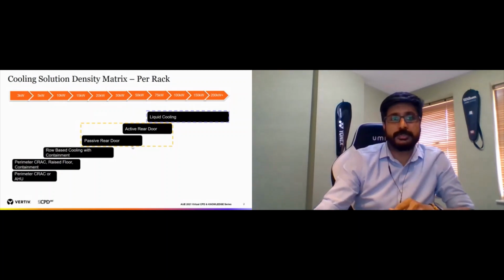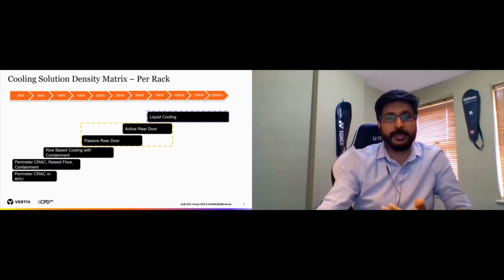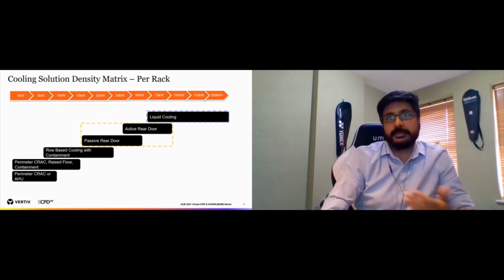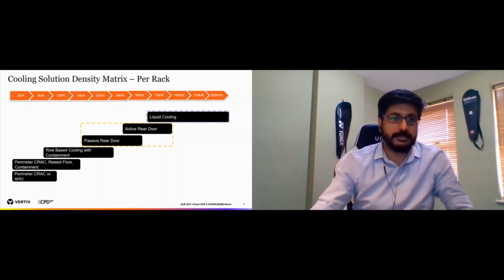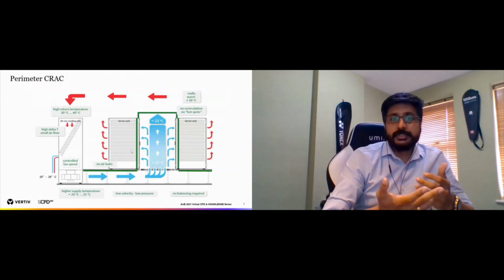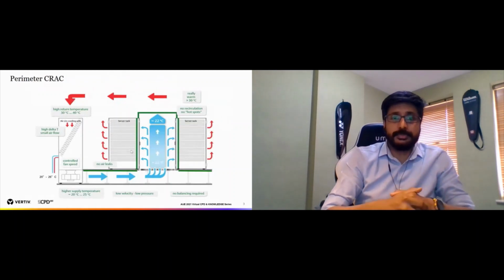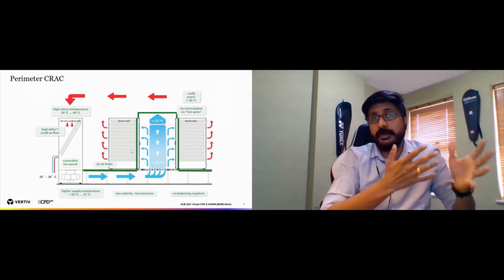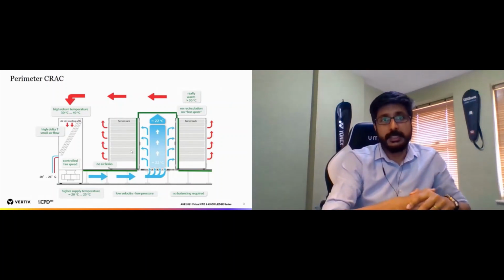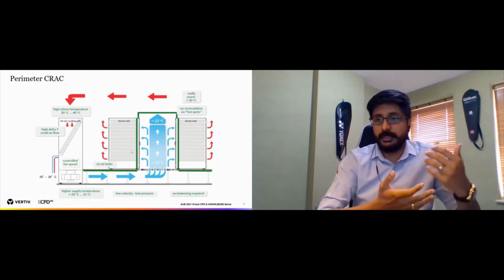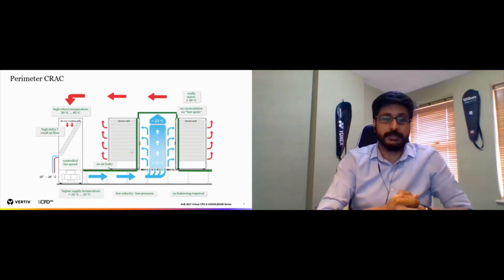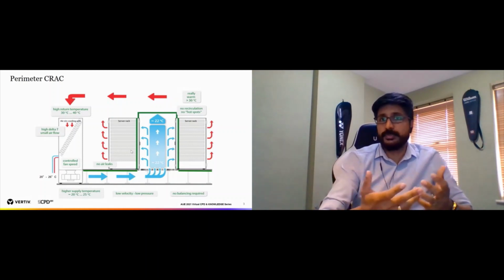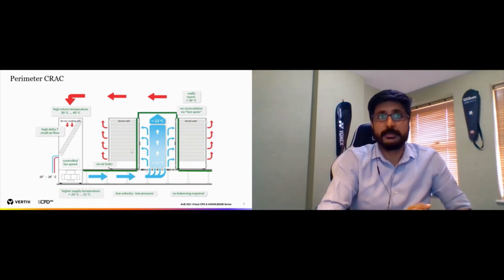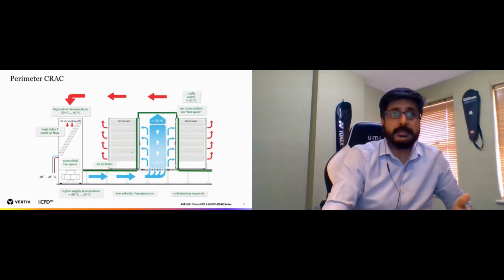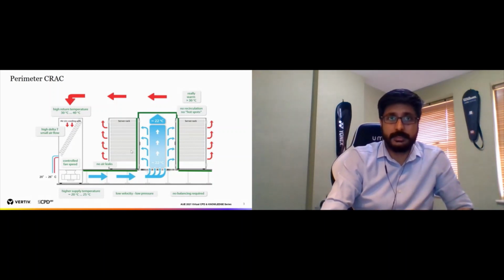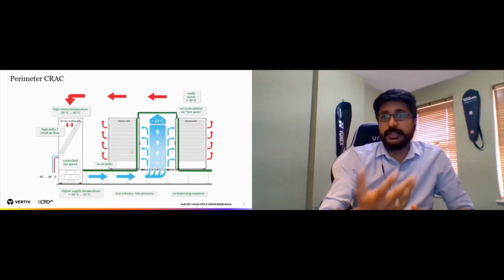So, just to go through the initial, historical way of cooling things, which might still be continuing in most applications as well. Traditionally, it was always a perimeter cooling solution, where we have a perimeter or CRAC unit sitting on one of the sides of the data hall, blowing air into the floor void, and the pressurized air comes out of the floor void through the grills and goes into servers. Servers get cooled, hot air comes back into the CRAC units, and this gets cooled again, and circulation goes on and on. So that was a traditional system.